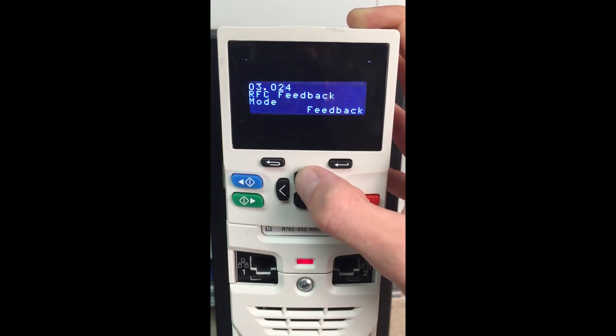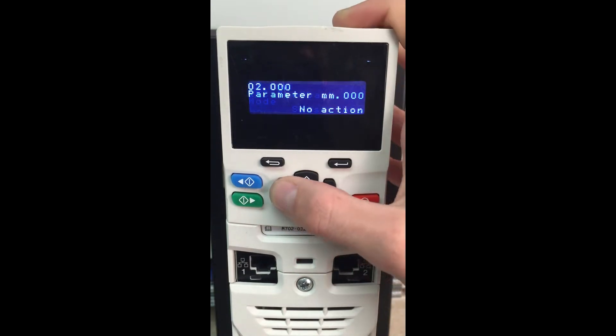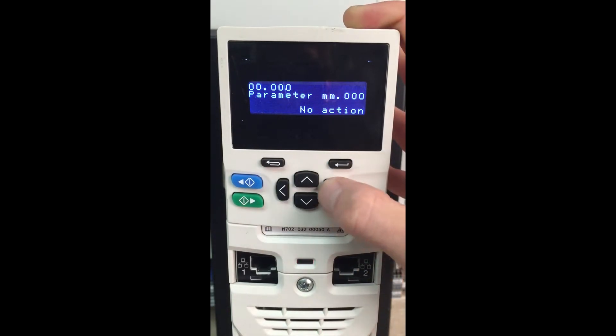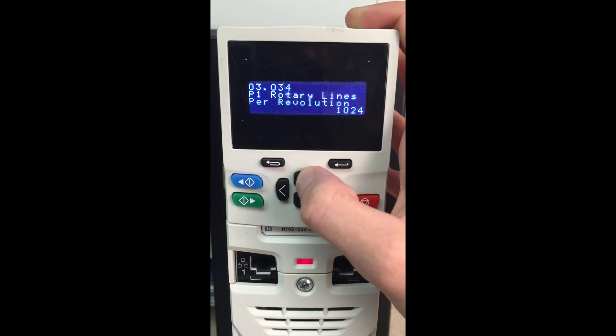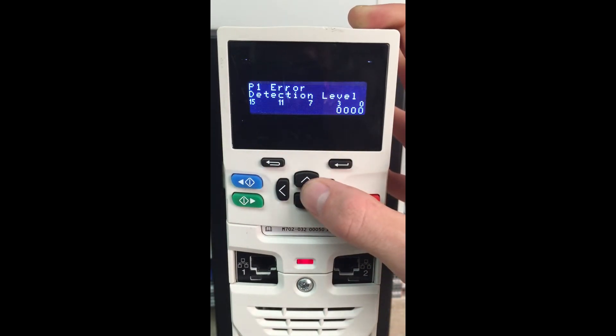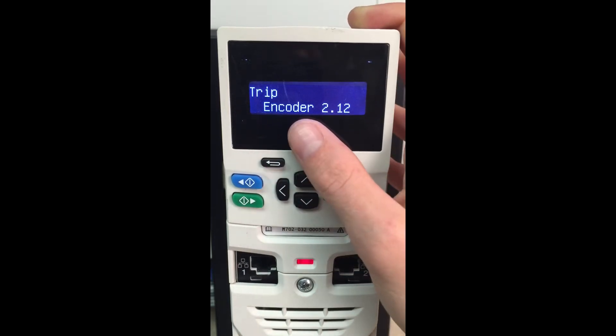Since we're doing sensorless, we're going to come over here to menu 3 and change our RFC feedback mode from feedback to sensorless. We're going to change that, come in here and do a parameter save. One thing you will want to do — as you can see, I do have an encoder trip. This is basically saying that there's a wire break; it's looking for that encoder and it doesn't see it, so it gives you a trip. What we're going to do is turn that off — set P1 error detection level to 0. What this does is it no longer will start referencing that encoder port trying to look for the encoder.